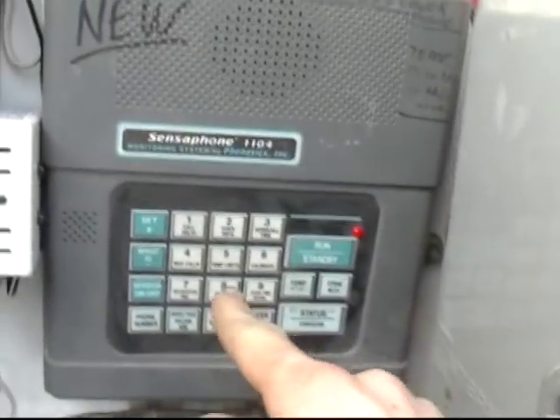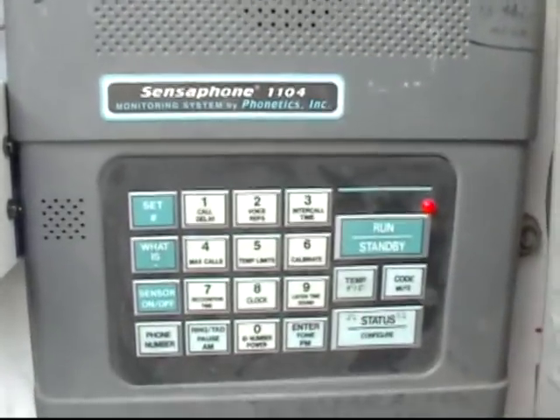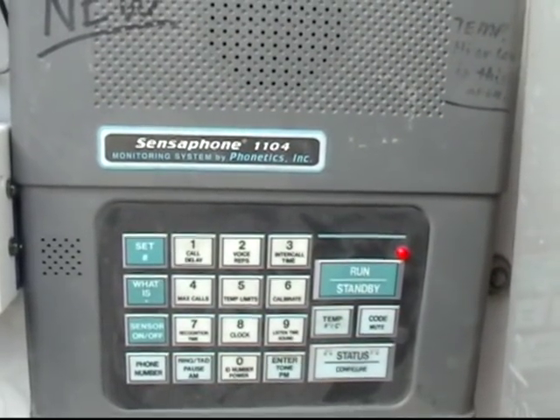Now that we've received the alarm, let's go ahead and set this back. The test has completed successfully. We'll go back and reset the alarm. Now let's check the status. The time is 9:04 AM. Number one — 67 degrees, that's the current temperature. Number two, okay. Number three, okay. Number four, off. Sound level, okay. Electricity is on. Replace batteries. Sound level, okay. We're good. Everything's working fine.